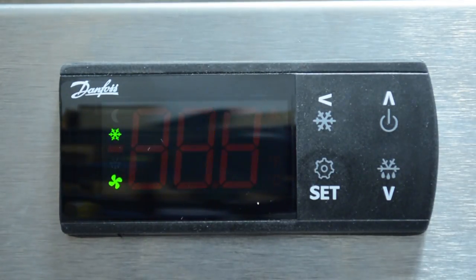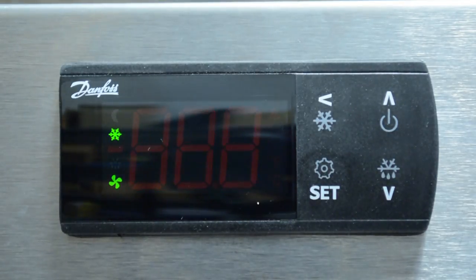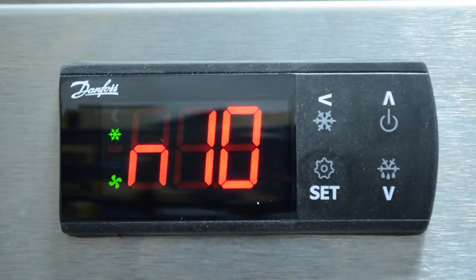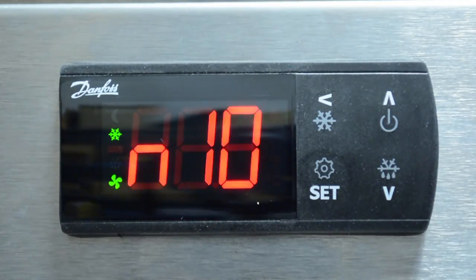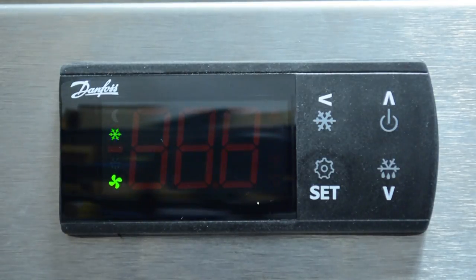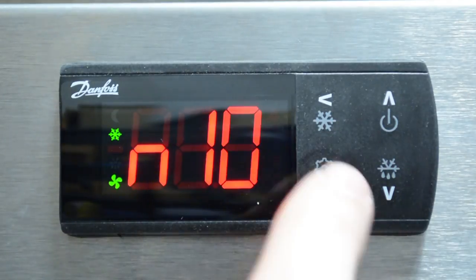If using a sensor already in the system, identify the sensor type using one of two methods. One, Remove the sensor and identify its type using the sensor resistance selection table included in the instructions. Or two, cycle through the four sensor options by repeatedly entering the quick menu and selecting a different sensor until the temperature reading is accurate. In this example, we know that we are using an NTC 10,000 sensor, so we'll select N10. Cycle between options by pressing the up or down arrow and press set to save.